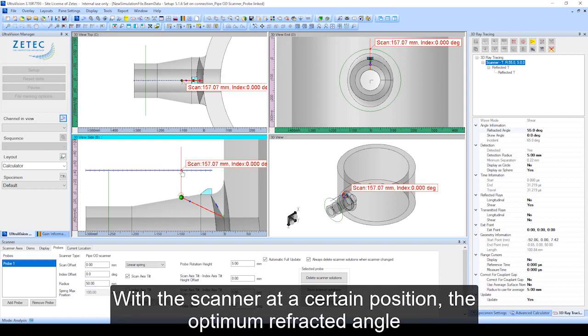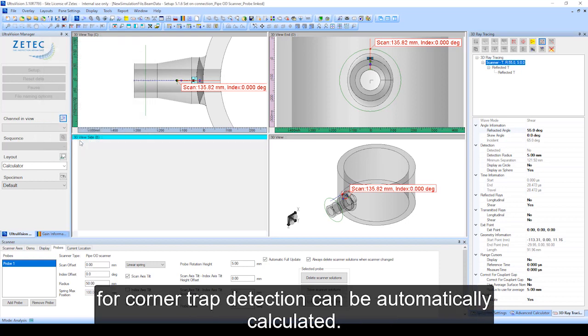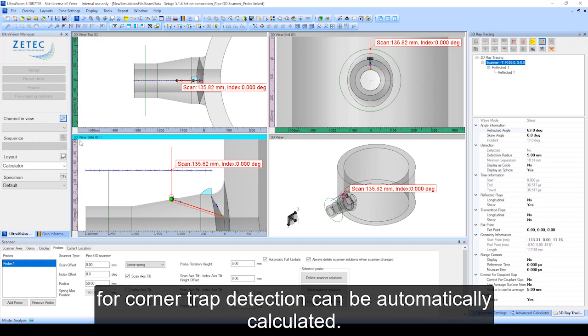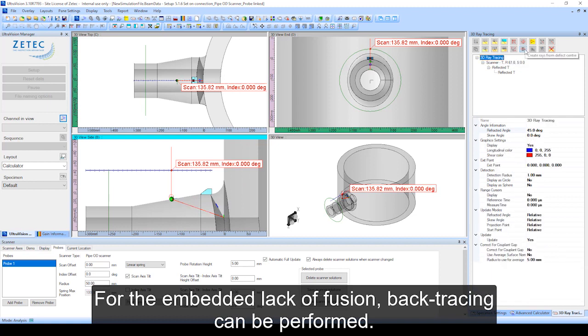With the scanner at a certain position, the optimum refracted angle for corner trap detection can be automatically calculated. For the embedded lack of fusion, backtracing can be performed.